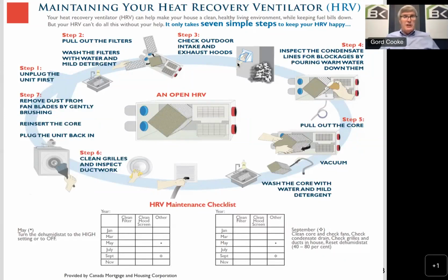This is a little sign CMHC created that you could hand to occupants. From the top left, it shows step 1, unplug the unit, pull out the filters, check the outdoor hoods, inspect the drain lines, pull out the core, vacuum it, sometimes wash it, clean the interior grills, and plug the unit back in. Not so bad, right? A nice little piece.